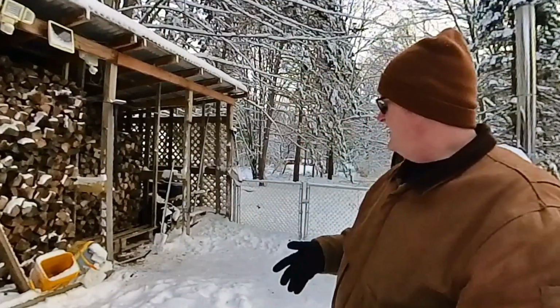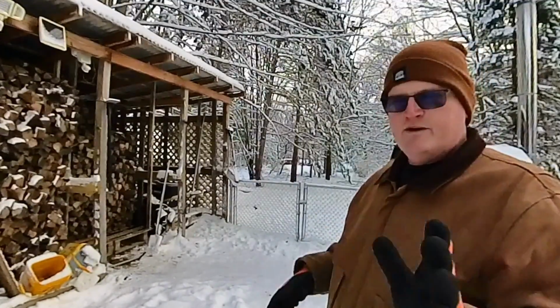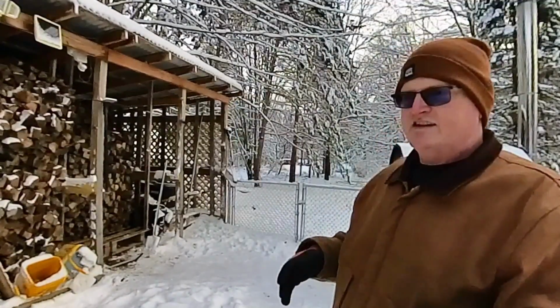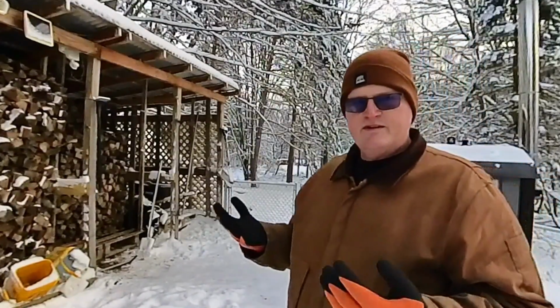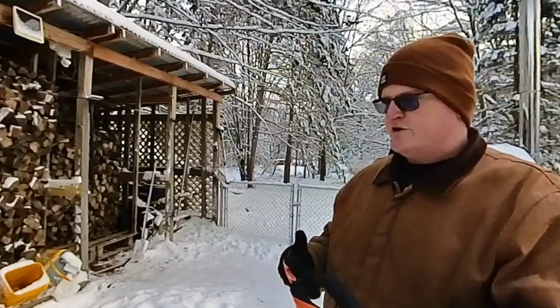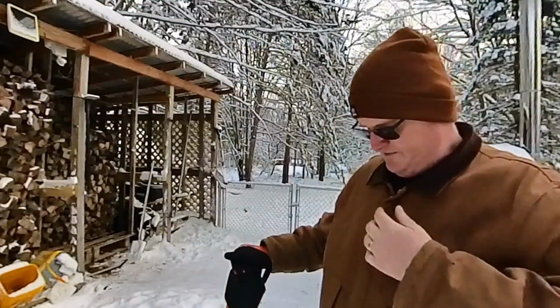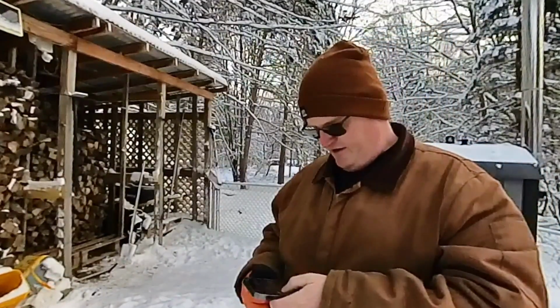Now, like I said, I don't know if Central Boiler has figured out this issue and fixed it already. I am going to tag them on this video just so they can see this. Maybe they'll chime in with some pointers. But the only thing I've been able to find is to pay attention to the reaction chamber temperatures, which on Central Boiler is a matter of just looking at an app, and I'll pull it up here.